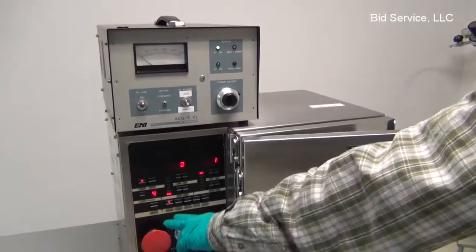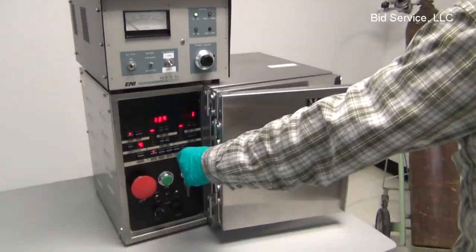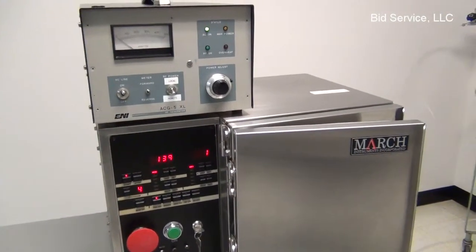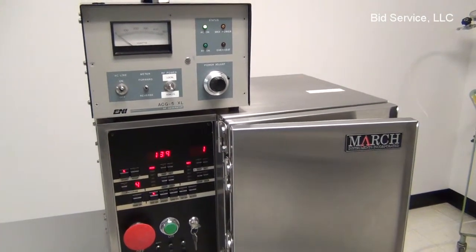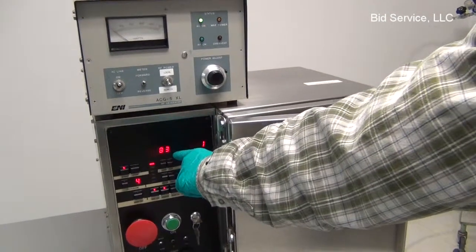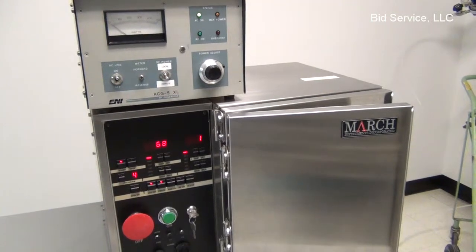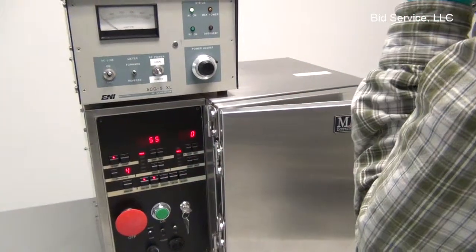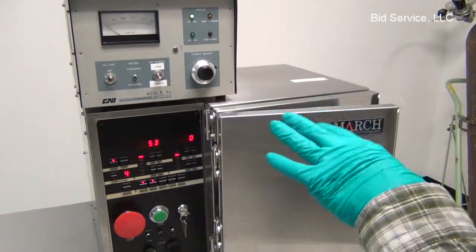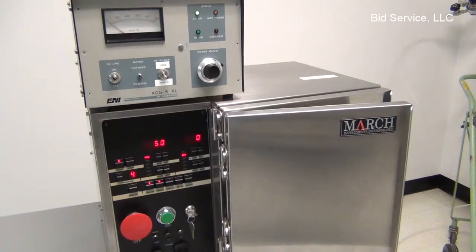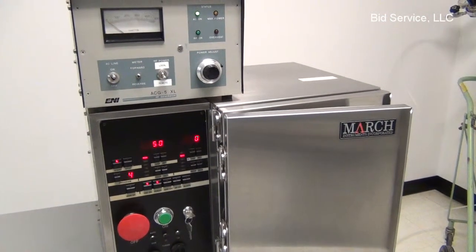And we're in a pump out stage of program 4. Now it's looking for the base pressure of 80. Once it comes below that, it'll turn the gas on. In this case, we got gas channel 2 on, which is just open atmosphere. So we're just going to bring air into the chamber.